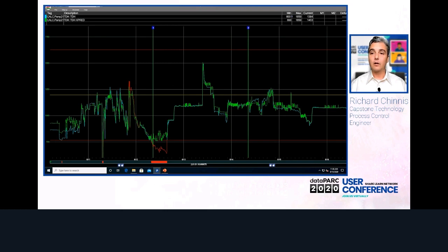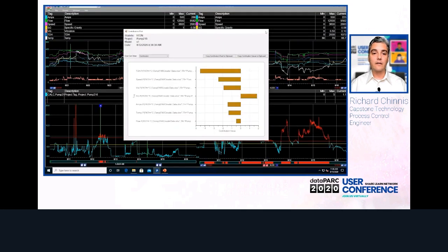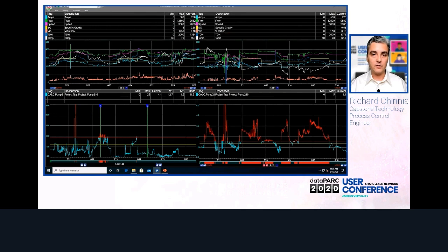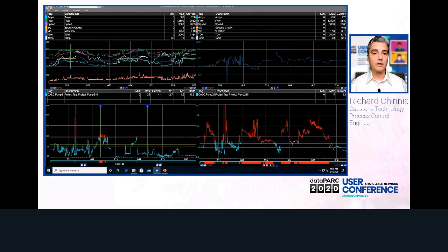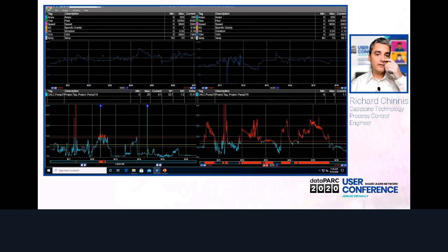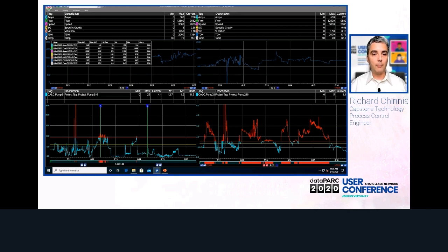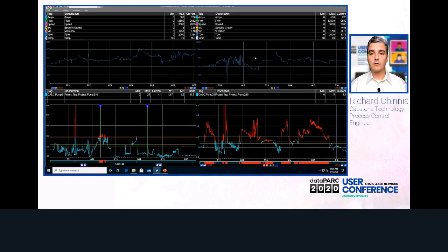But what we're looking at is the HT2N. So HT2N tells us that it deviated from the base data. So that's why I want to look up here. There's dynamic head. This is my base data. This is my evaluation data. So if I turn on quick statistics, the minimum total dynamic head was 923, okay? But if I turn on Smart Mouse over here, I can see my total dynamic head was getting down under 700.